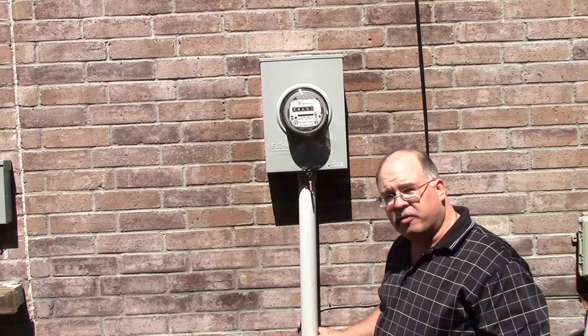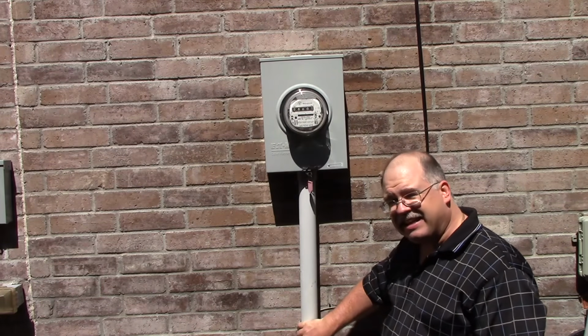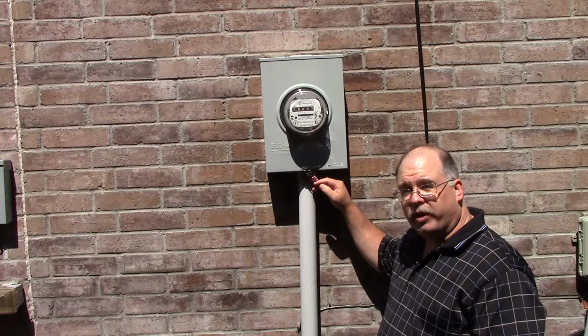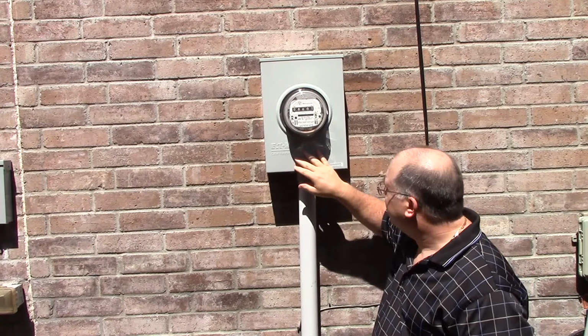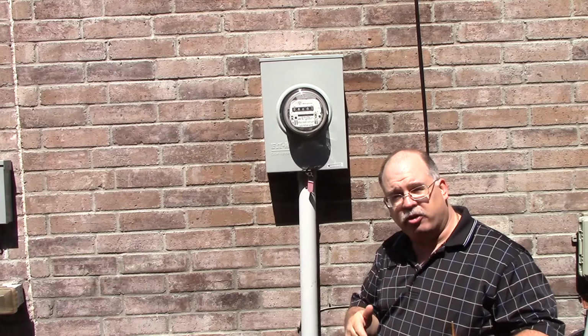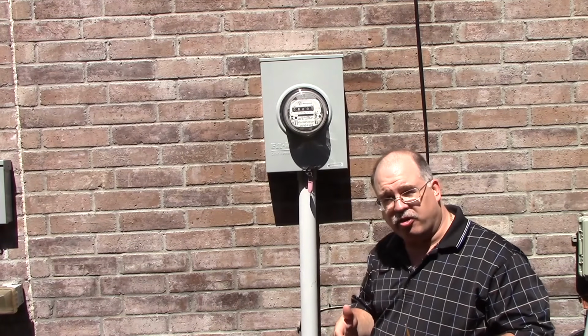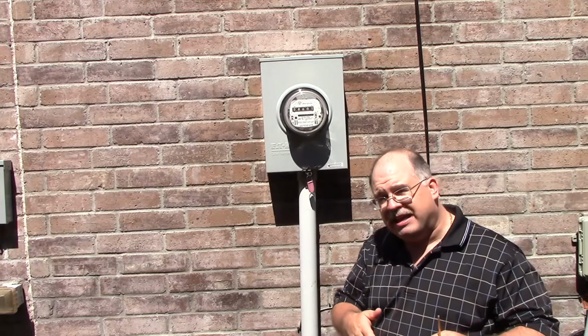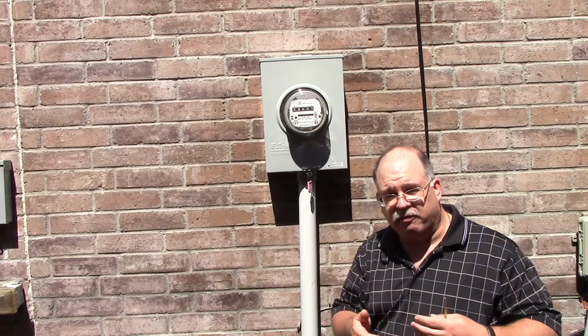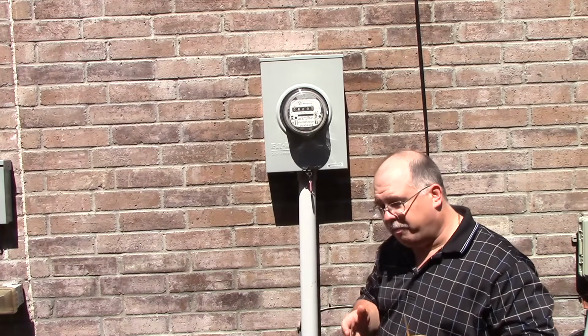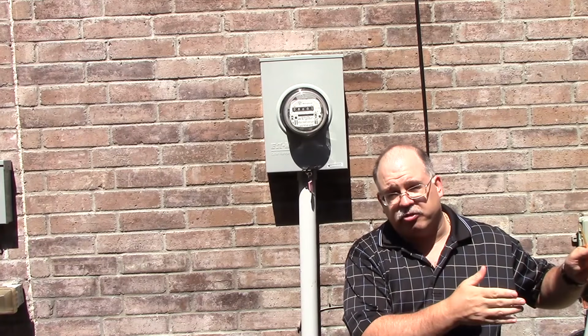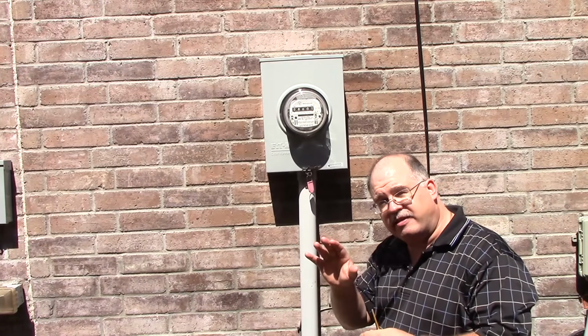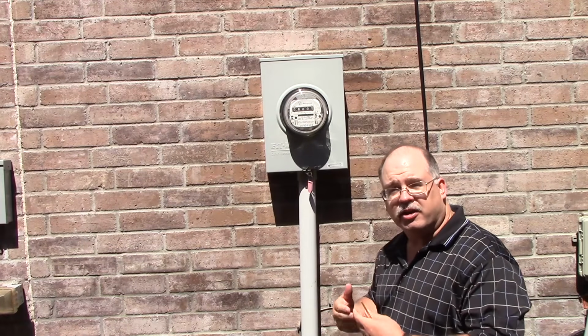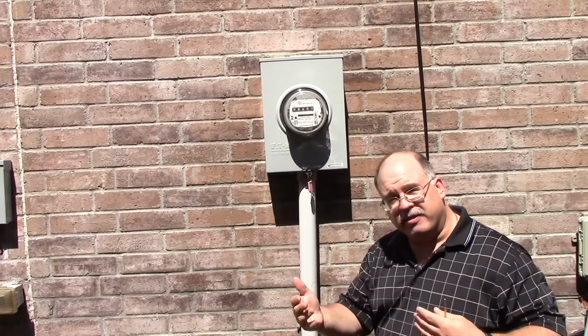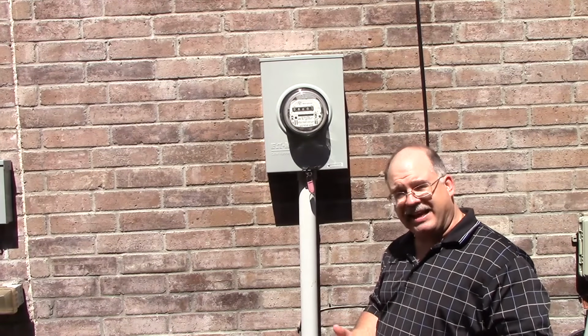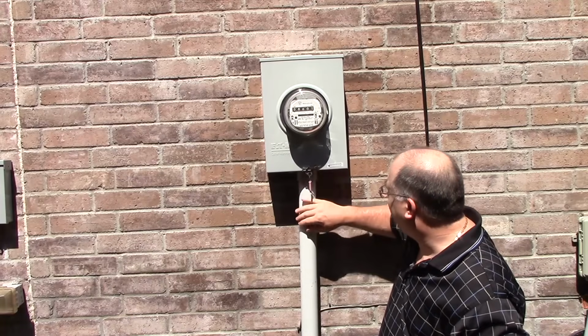Okay. And for a municipal inspector, you have to remember that this is a service lateral, so this is technically outside the scope of the National Electrical Code up to this point, whereas the actual service point is right here. Of course, that depends on where your transformer is on the property and whose control it's under. It might be service entrance conductors underground versus service laterals. If there are service entrance conductors underground, they're going to come under the NEC. If it's a service lateral, it's outside the scope of the NEC. The burial depths on that are governed by the National Electrical Safety Code, whereas 300.5 and its associated table cover the burial depth for service entrance conductors underground. So there's a difference in that. But as a home inspector, you're not going to see that anyway. We're just looking for any damage. So this looks okay. Everything looks fine.